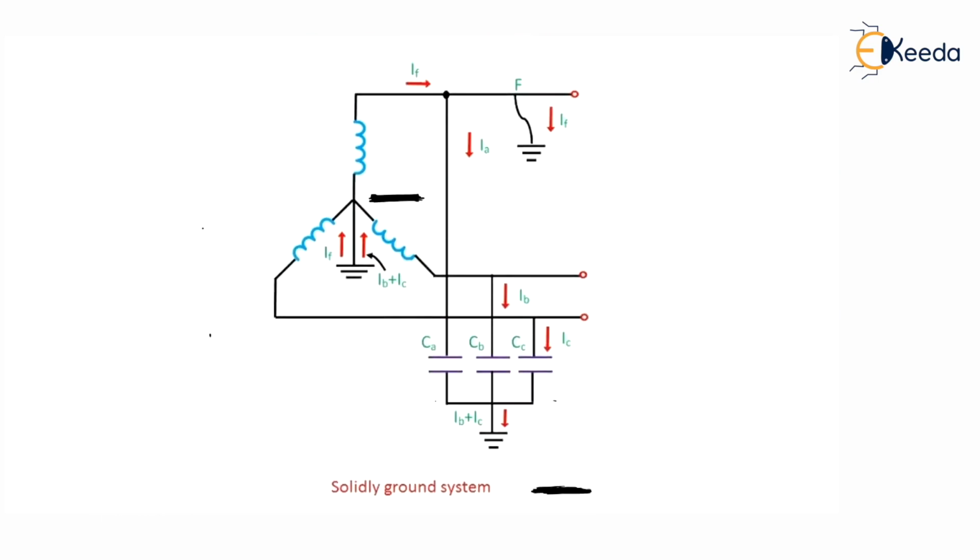So see in this figure, this system consists of 3 phases, phase A, phase B and phase C. So if the single ground fault occurs in phase A, in phase A, the voltage of the phase becomes zero. However, the remaining 2 phases, phase B and phase C, will still have the same voltage as before. So when the fault occurs in the system, in addition to the charging current, the power source also feeds the fault current.